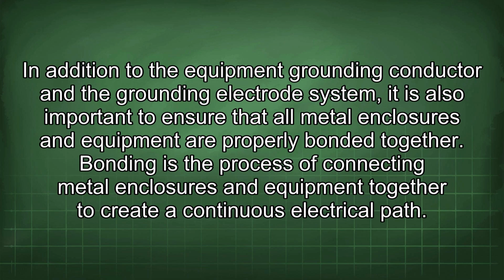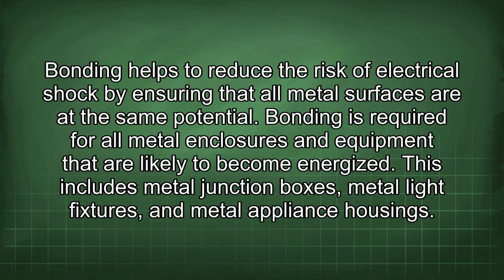In addition to the equipment grounding conductor and the grounding electrode system, it is also important to ensure that all metal enclosures and equipment are properly bonded together. Bonding is the process of connecting metal enclosures and equipment together to create a continuous electrical path. Bonding helps to reduce the risk of electrical shock by ensuring that all metal surfaces are at the same potential. Bonding is required for all metal enclosures and equipment that are likely to become energized. This includes metal junction boxes, metal light fixtures, and metal appliance housings.